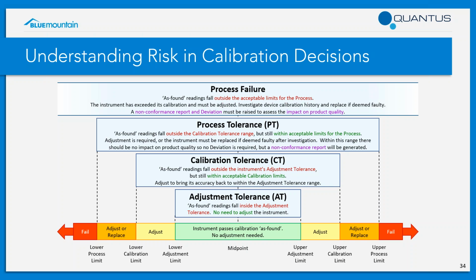And up at the very top of the diagram, we find process failure. So in this case, the as found readings would fall outside the acceptable limits for the process. On the colored bar at the bottom, the as found readings would fall into the red areas on the far left and the far right of that band. In this case, the instrument has exceeded its calibration and must be adjusted.